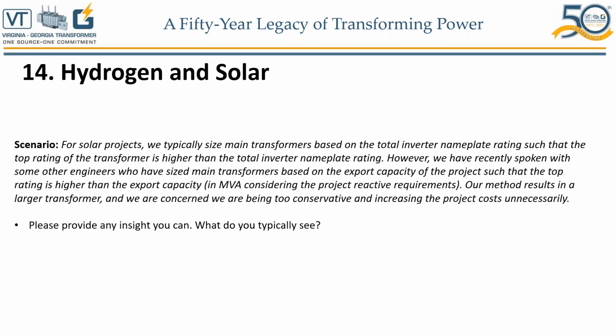Next one. For solar projects, we typically size main transformers based on the total inverter nameplate rating, such that the top rating of transformers is higher than the total inverter. However, we have recently spoken with some engineers who have sized main transformers based on the export capacity of the project, such that the top rating is higher than the export capacity. Our method results in a larger transformer, and we are concerned we are being too conservative and increasing the project costs unnecessarily. Please provide any insight you can. What do you typically see?